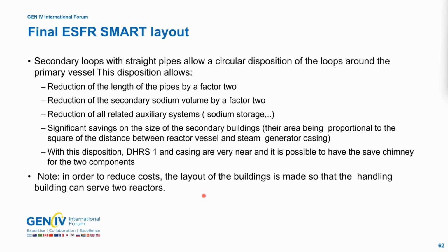We have significant savings on the size of the secondary buildings, about 50% also, because their area is proportional to the square of the distance between reactor vessel and steam generator casing. With this position, the DHRS1 and casing are very near, and so it's possible to have the same chimney for the two components. And we can also note that in order to reduce the cost, the layout of the building is made so that the handling building can serve for 2 reactors.